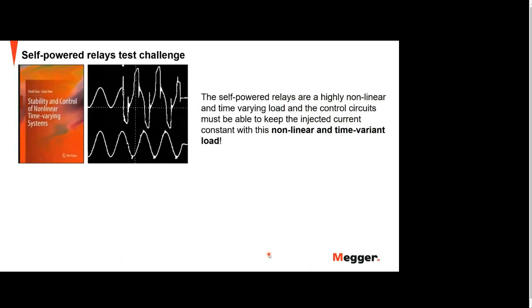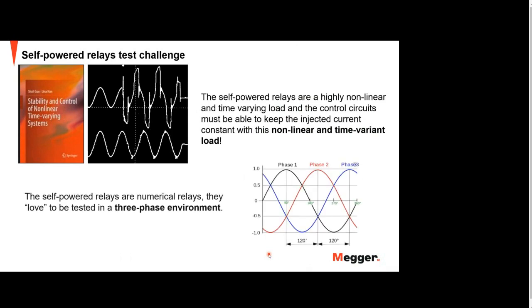Also, the challenge with testing self-power relays is the highly non-linear and time-varying load, and the control circuit must be able to keep the injected current constant with this non-linear and time-variant load. So that's the tricky thing with this. And with the Sverker 900, we have the opportunity to test three-phase also, because normally that's the best way to test the self-power relays, because then it can take power from all three phases, which helps the self-power relays get the power to itself.